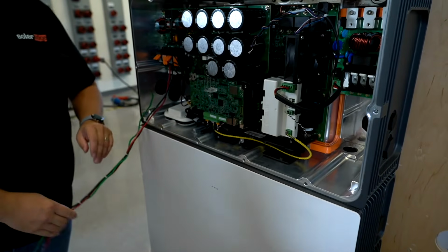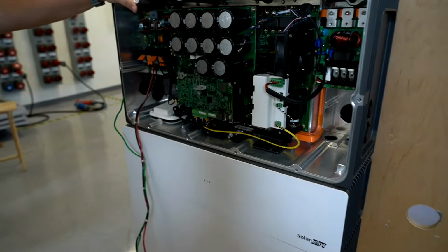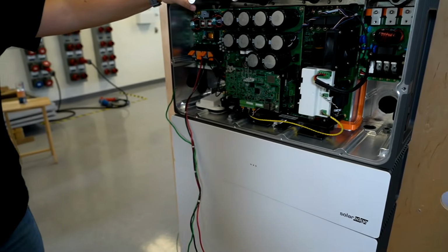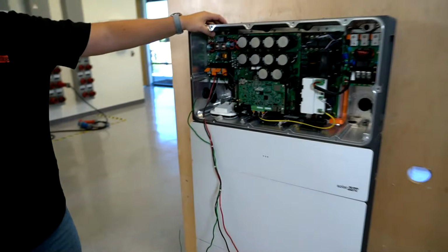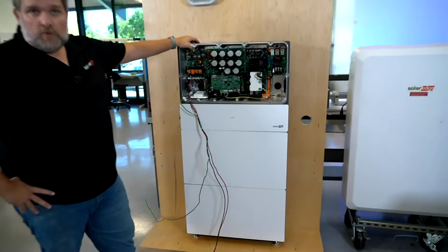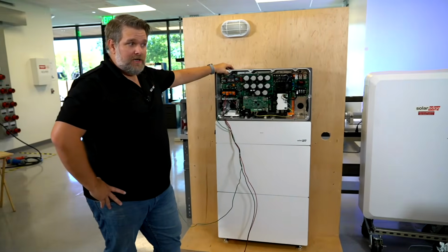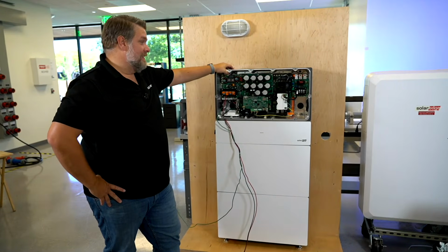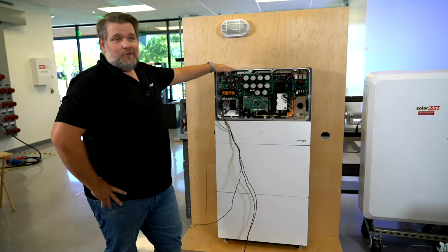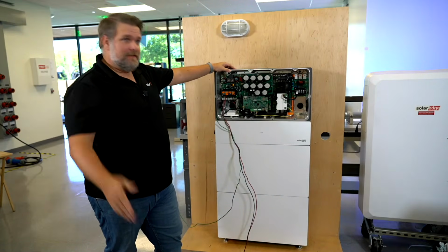Does that count as separation? Yeah—so the code says that if you're going to have AC and DC conductors in a raceway, they have to have separation unless that raceway is listed for that purpose. Well, guess what—an inverter is listed to mix DC and AC.